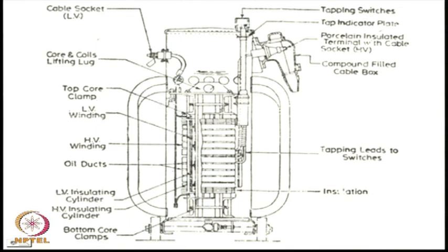So, this is the top core clamp, this is the LV winding, this is the HV winding, between HV and LV there are oil ducts, this is the LV insulating cylinder here, this is the HV insulating cylinder here, the bottom core clamp, and these are the tappings, these are different insulating materials. Now, this does not show a bushing because the underground cables may be connected through this cable box, and this also has a porcelain insulating terminal, but does not show a bushing, and there is a provision for seeing where the tap position is, and this is the tap switch. This is one view of the transformer.